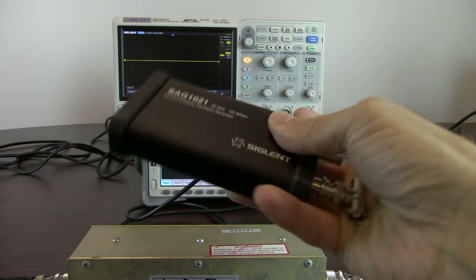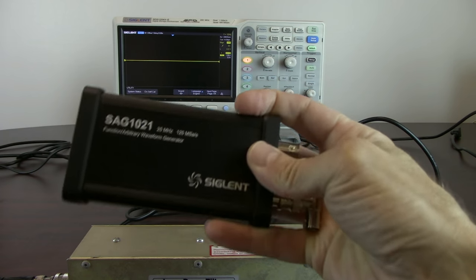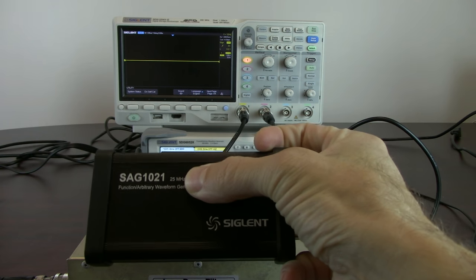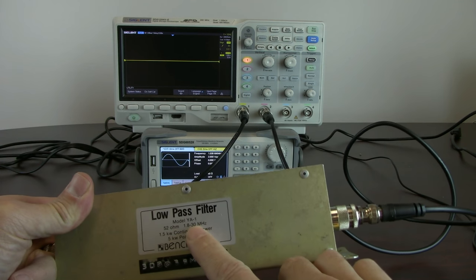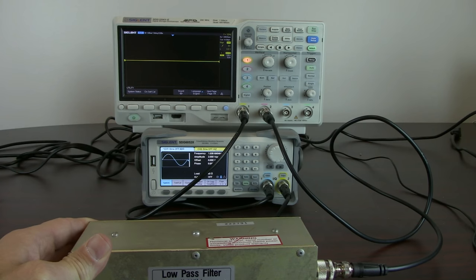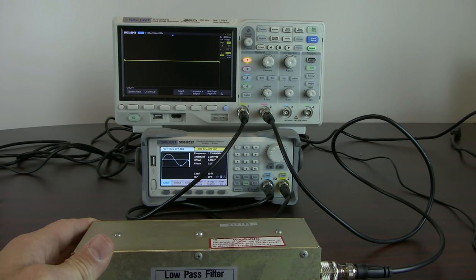This test can also be run using the standalone SAG-1021. This is an accessory for the four channel XE. This goes up to 25 megahertz. The reason I'm not using it for this particular test is this is a 30 megahertz filter, so we need to go beyond 30 megahertz in order to see the filter effect on the frequencies as we're going through.